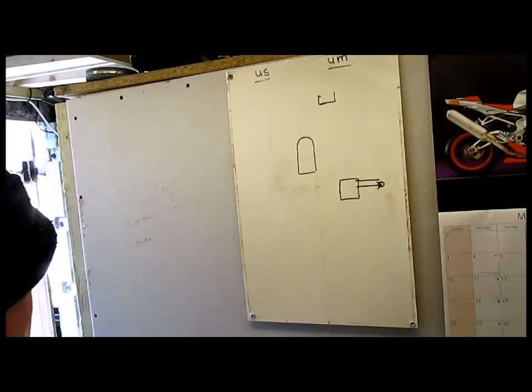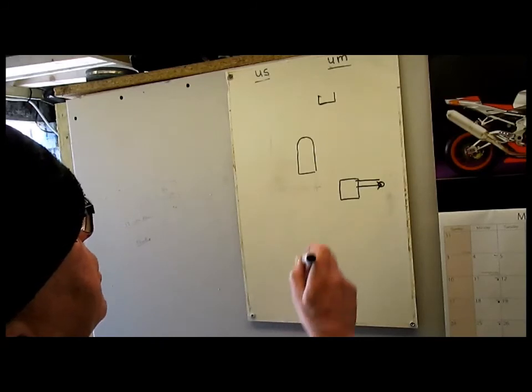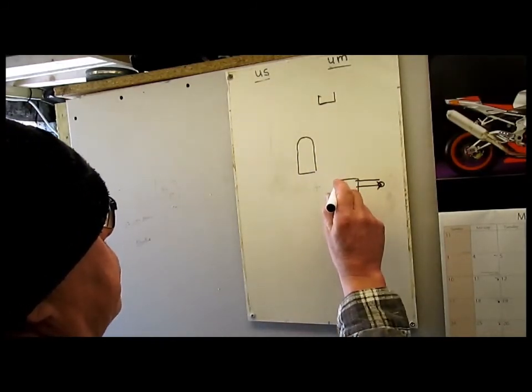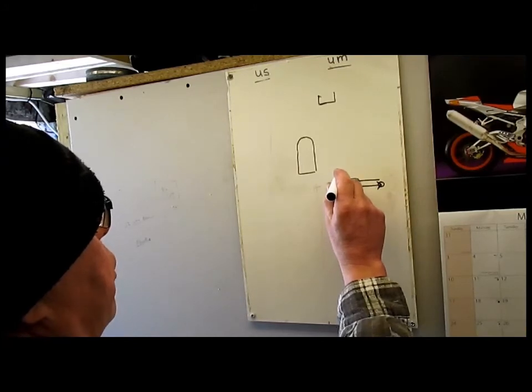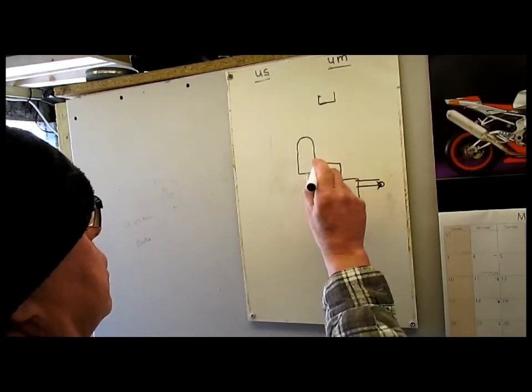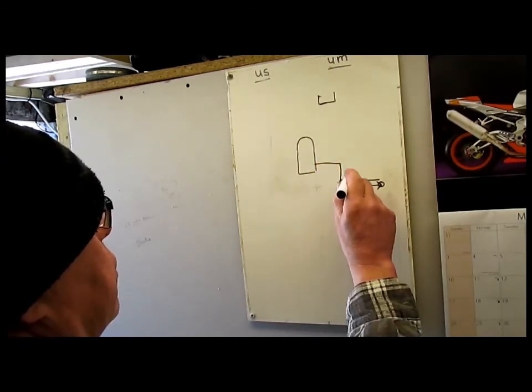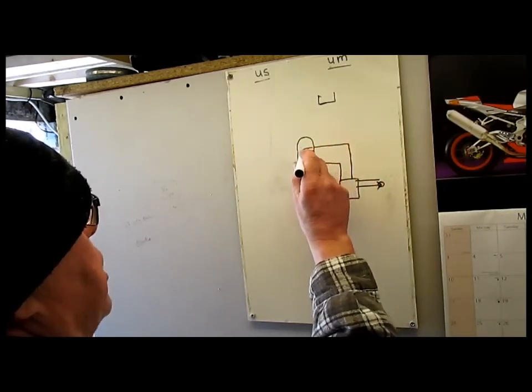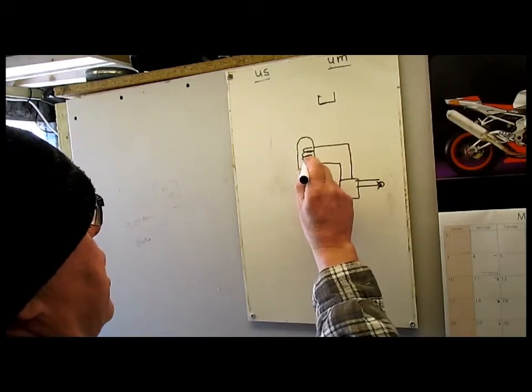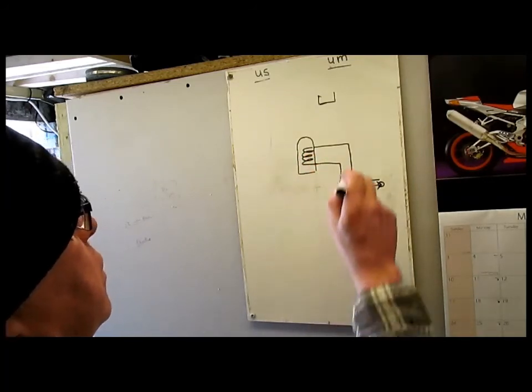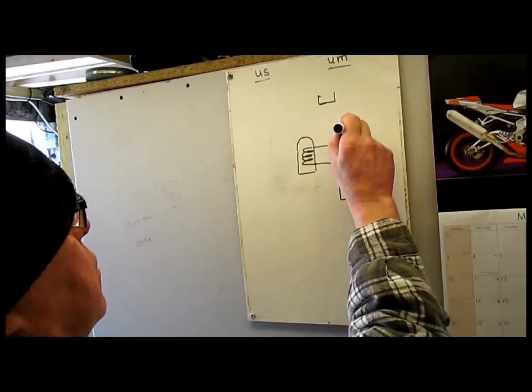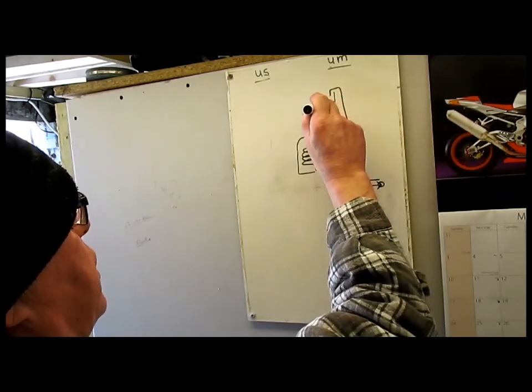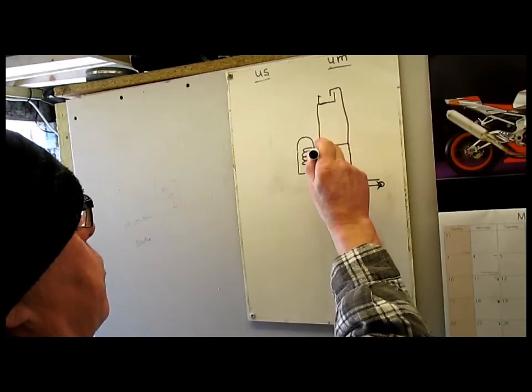But when we refer to hot water heating as gravity, we're talking about the water that's going from the boiler to the cylinder. There, in the cylinder, there's a coil into the cylinder, so it's separate from the hot water that's coming out of the taps. It's a separate water, and you have a vent over that tank and a cold feed going into the tank.